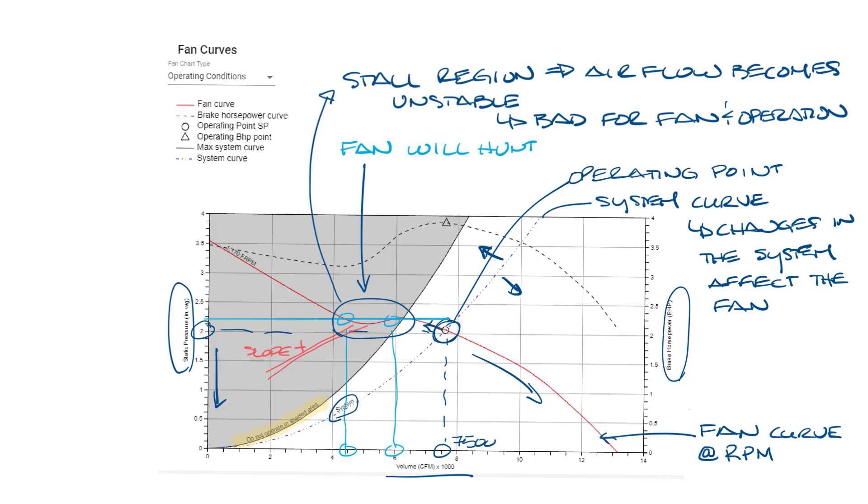If you add pressure drop to the system, the system curve could shift over here, and now you see that your operating point is at a lower CFM. And now your fan is not producing as much air as you need, or if you're close enough to this gray area, you could end up in the do not operate area of the fan curve.